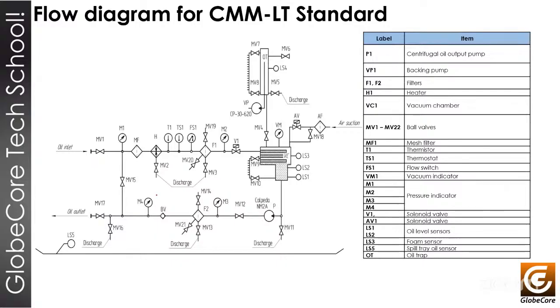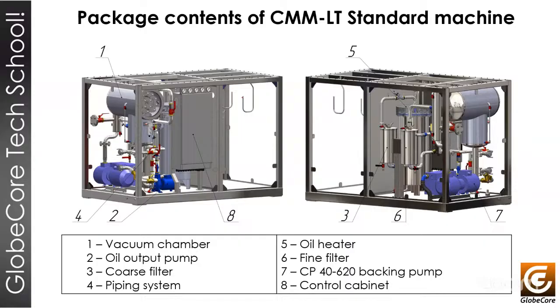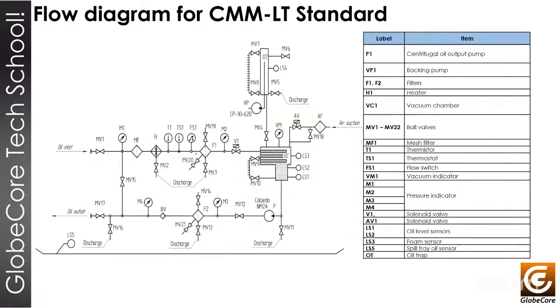Okay, here we have the flow diagram of the LT standard machine, CMM LT standard. That is the machine that has the frame for storage, hoses, power cable and tools. And it's really easy. You will have the same flow direction. Okay, the oil will pass through the valves, through the filter, through the heater, another filters, and then will reach the vacuum chamber. This vacuum chamber is the big one, the vacuum chamber that has the flow in 3 different columns. I explained before in this presentation.